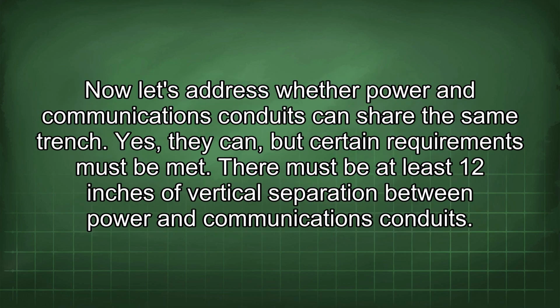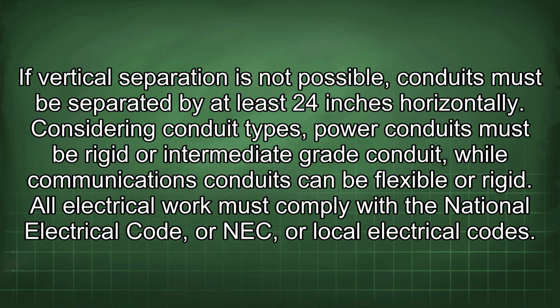Now let's address whether power and communications conduits can share the same trench. Yes, they can, but certain requirements must be met. There must be at least 12 inches of vertical separation between power and communications conduits. If vertical separation is not possible, conduits must be separated by at least 24 inches horizontally.